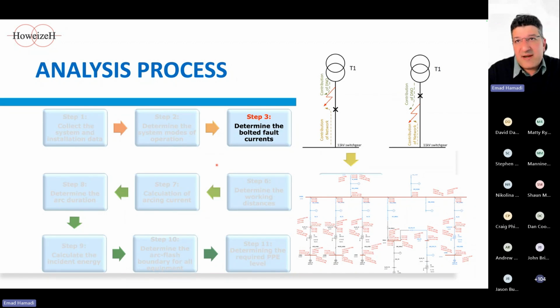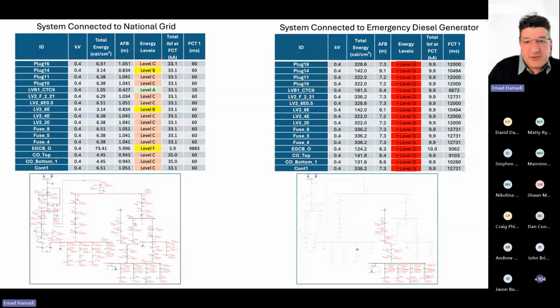You need to consider everything: the motors, the generators, everything that could potentially contribute to the point of the fault in terms of short circuit needs to be taken into account. You can find the short circuit level everywhere in the network, and based on that you run your arc flash study. It is also important to find the higher and the lower short circuit levels, because a lower fault current may result in longer opening time for the overcurrent protection devices, therefore increasing the incident energy. This is an example where we found the incident energy level was considerably higher when the system was connected to the emergency diesel generator.